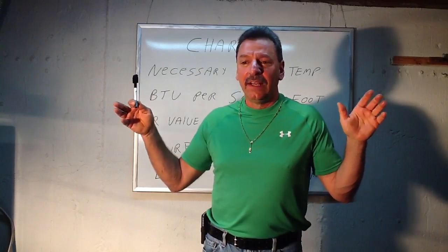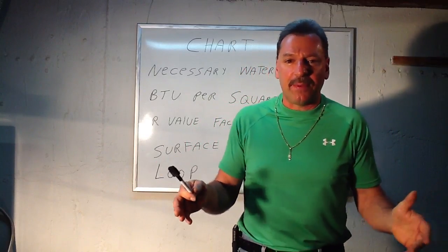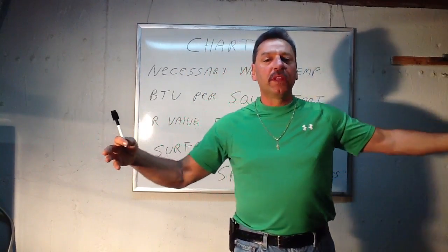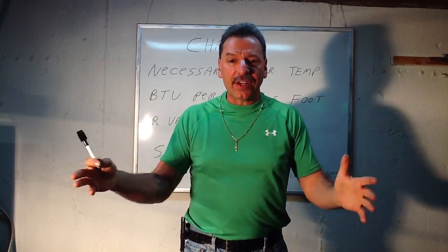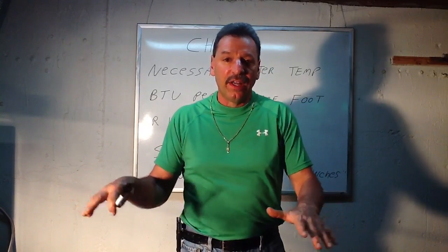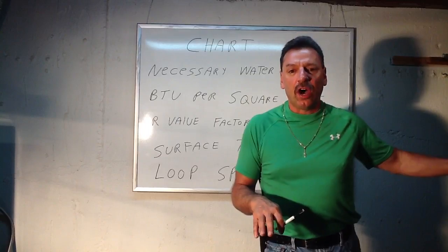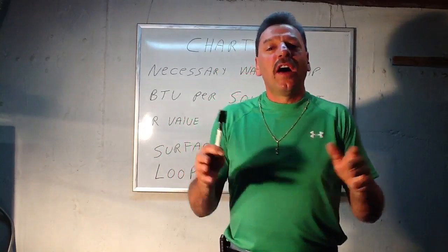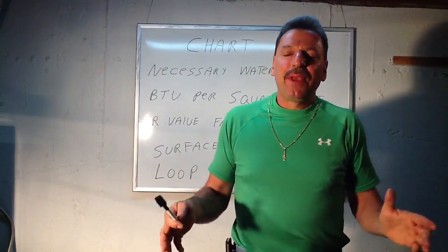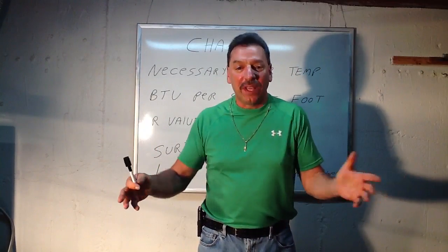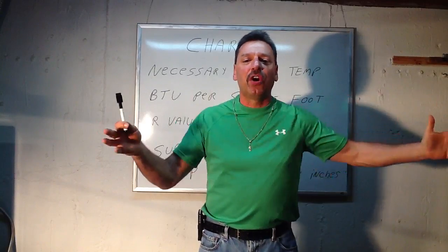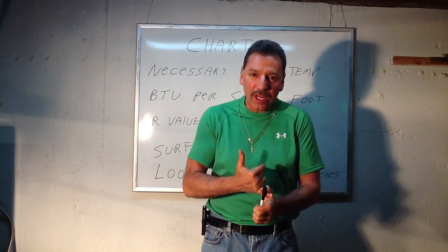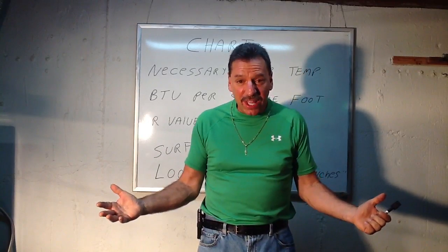Because with radiant heat, and I'll give you a simple example, you can't have a large kitchen with an open living room where the kitchen is mud and tile floor, and then the living room is a thin carpet, where that R value that we talked about is two different R values on the same zone. Because once it's on the same zone, even though they're close together and the rooms are open, there becomes this huge question. Where do you put the thermostat?